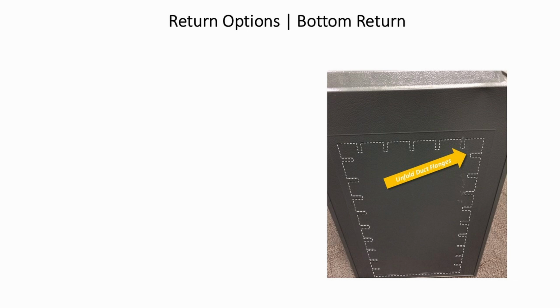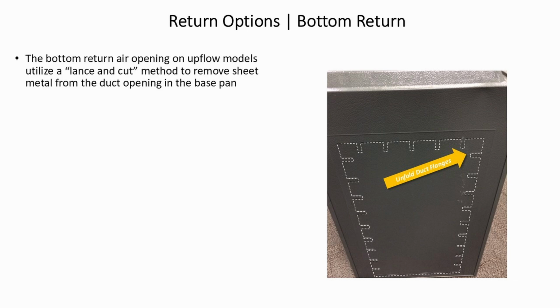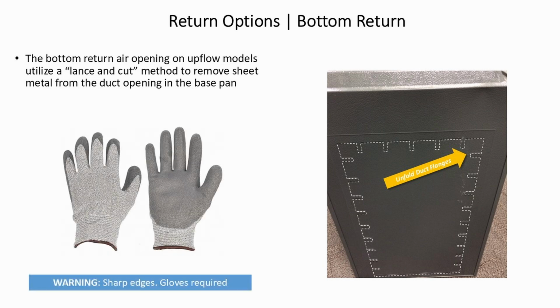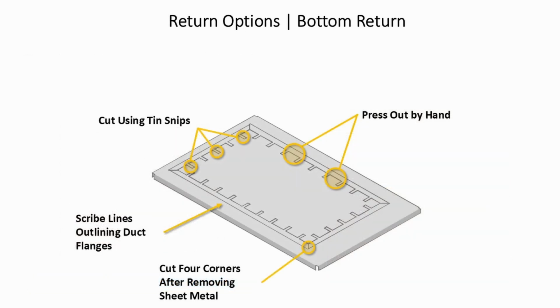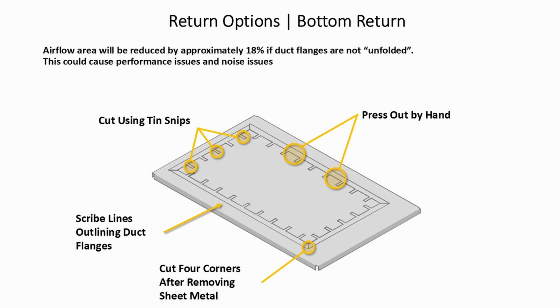Return air options. Bottom return. The bottom return air opening on upflow models utilizes a lance and cut method to remove sheet metal from the duct opening in the base pan. Warning: there are sharp edges, therefore gloves should be worn. Airflow areas will be reduced by approximately 18% if the duct flanges are not unfolded. Scribe lines outlining the duct flanges. Cut all 4 corners after removing the sheet metal. You can cut the tabs using tin snips or press them out by hand.